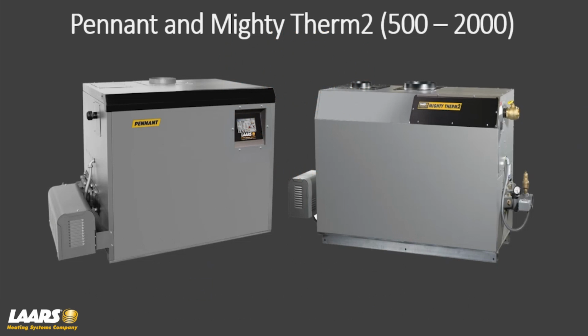We're going to talk today about the Pennant and MightyTherm2. The sizes we'll talk about range from 500,000 to 2 million BTUs. Now, both of these products are pretty much the same. They utilize the same heat exchangers, combustion chambers, gas trains, igniters, blowers, etc. What changes on the Pennant is the controls, basically.